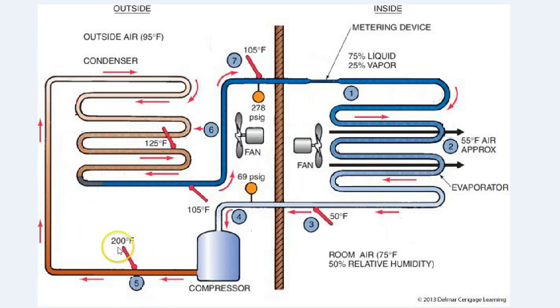At this point, we are 100% liquid. Now we begin the subcooling. Because we can't change state anymore and we are 100% liquid, any heat that is given off by the refrigerant is sensible heat.